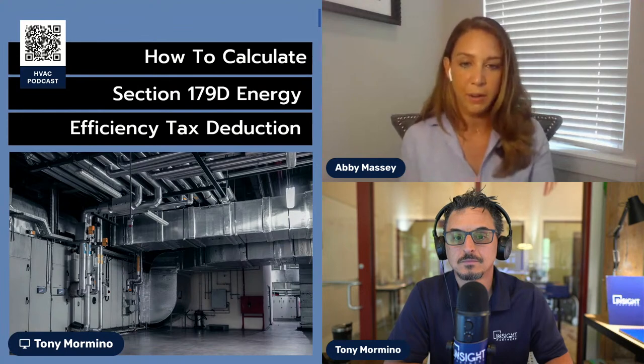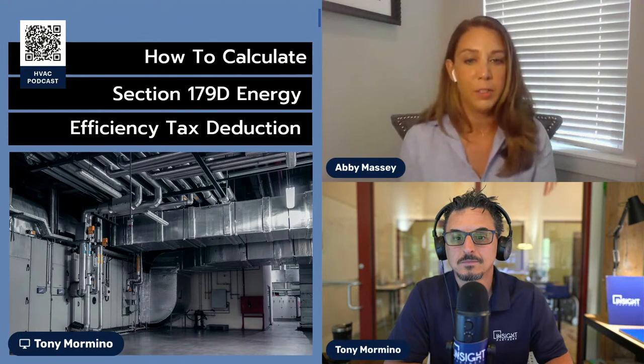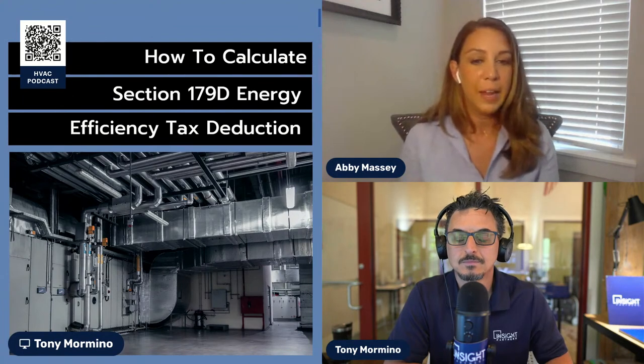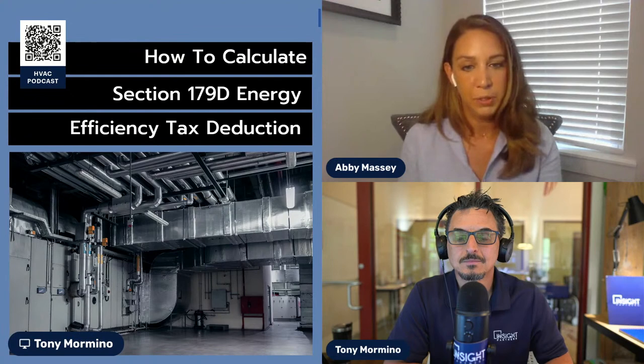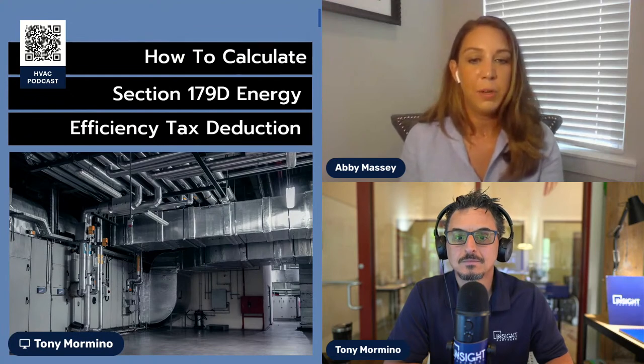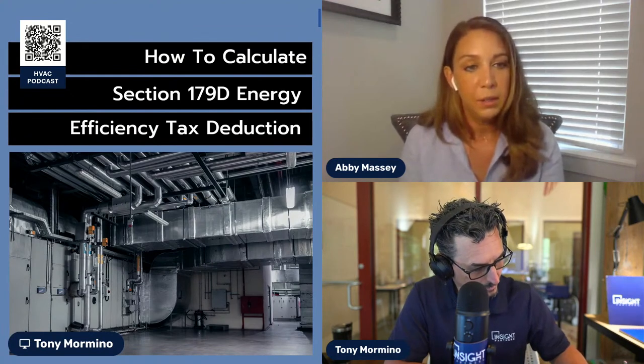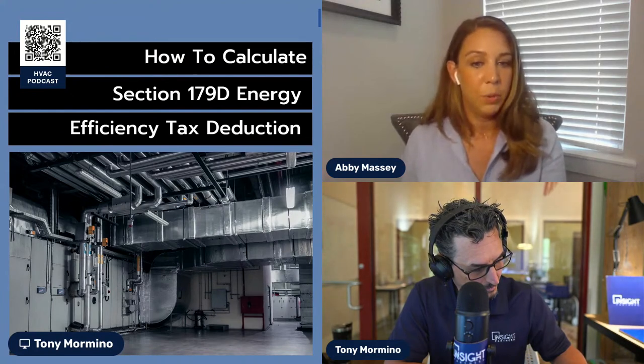Once we compare that actual building versus the ASHRAE 90.1 baseline standard, we're looking at the annual energy cost savings percentage. If that percentage is 50% under the old system, you would receive the maximum $1.80 per square foot.